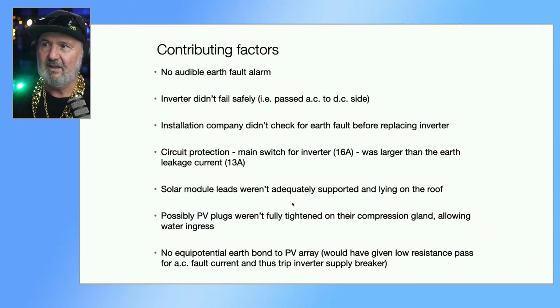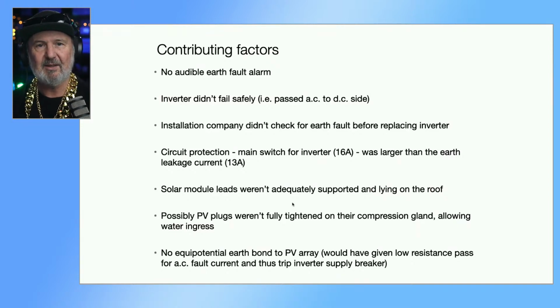So the upshot of it was, surprisingly, the overcurrent protection on the AC side didn't trip because it was a 16 amp breaker, which was correctly sized, but the fault current was only 13 amps AC because of the long path that it had to pass through to get back to the main switchboard. And it was assumed that possibly the problem was that the PV plugs weren't fully tightened. So there's a compression gland on the back of PV modules, and that needs to be, well, it should be done in the factory, but if you've made up any connections, then you've got to make sure those compression glands fully seal around the cable.